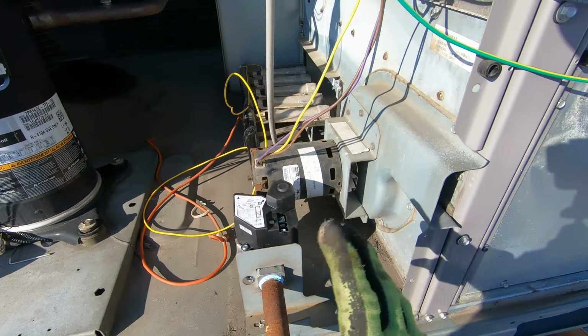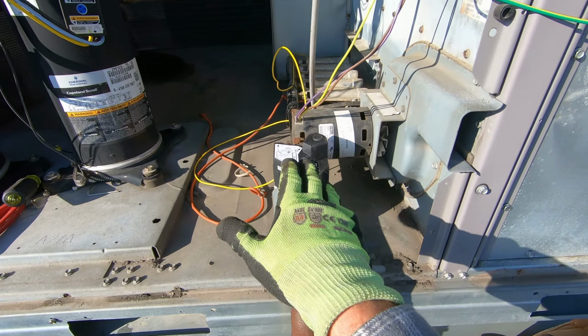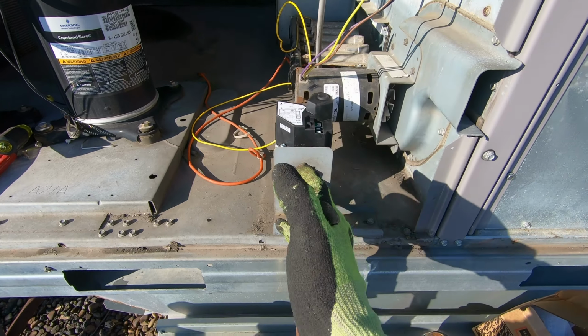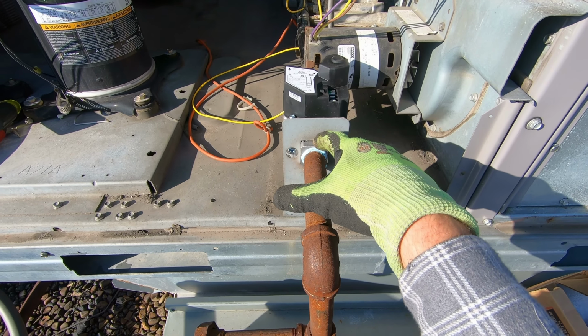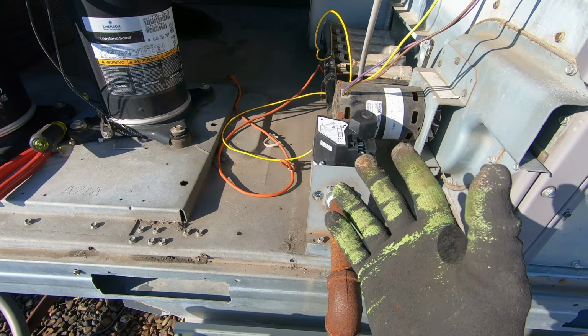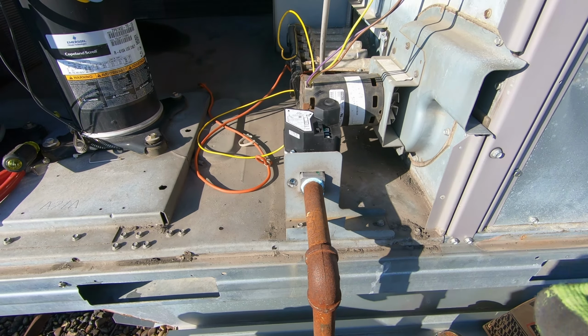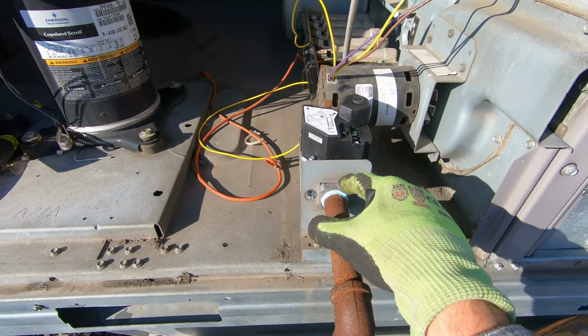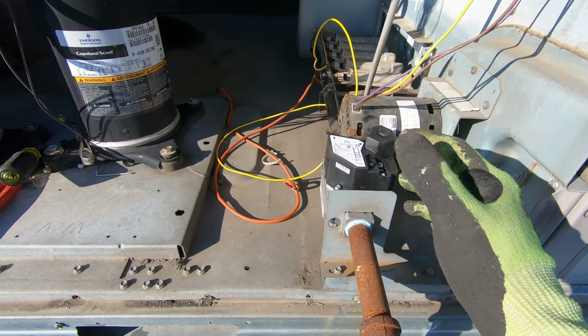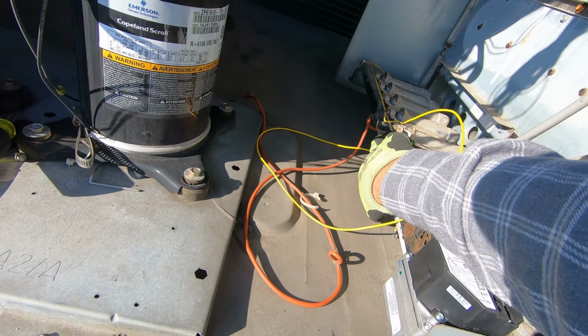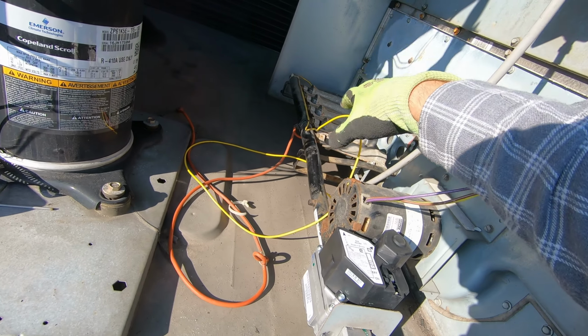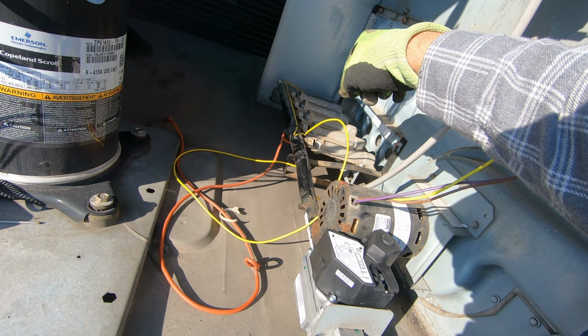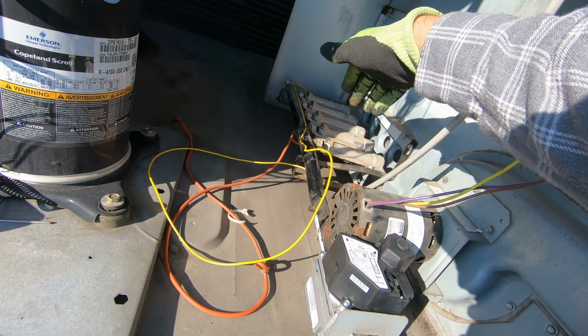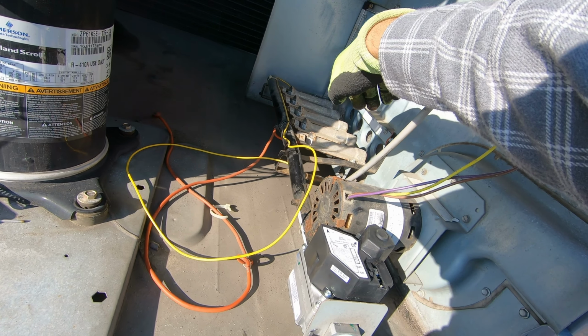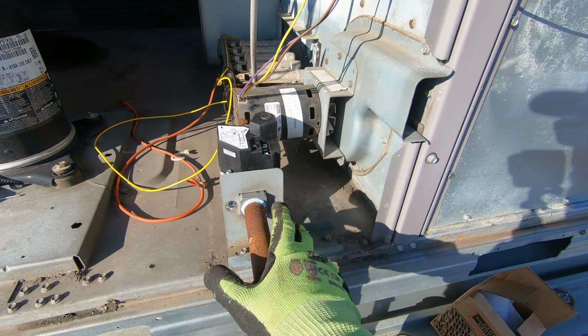Now the reason I waited to put this back in was because I wanted to make sure my gas valve was level and able to fit into this support bracket here. Because if you put it all together outside of the unit, and then try to get it in, you realize it isn't gonna fit in here, and you start torquing on it, you can mess up the way this burner bracket holds the orifices in the burners, and ultimately the way the burners are directed at the heat exchanger. That's why I did that.